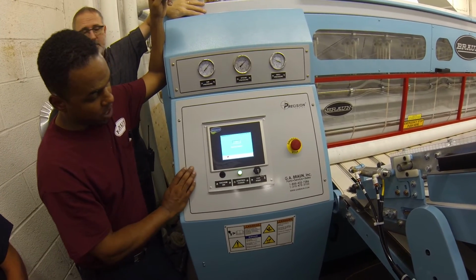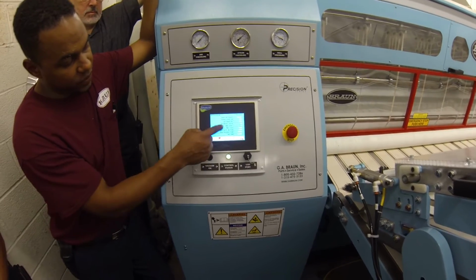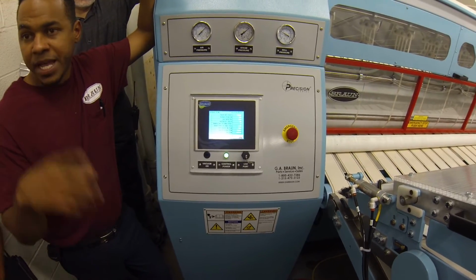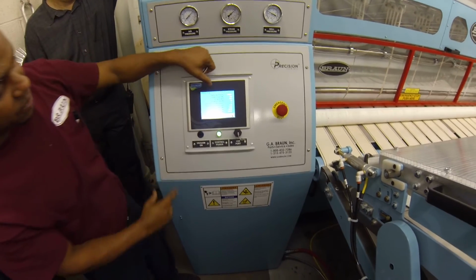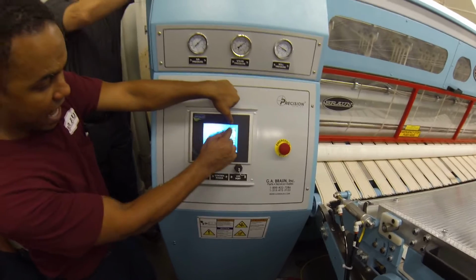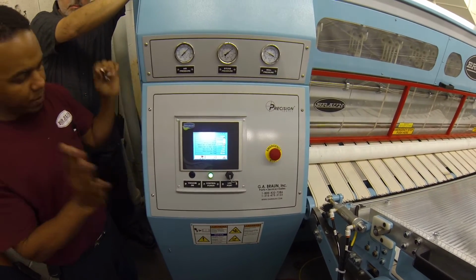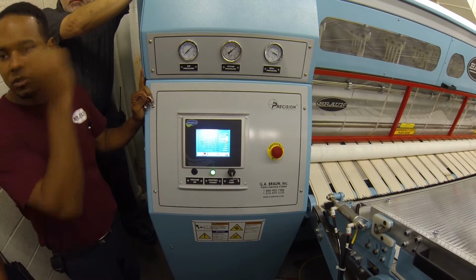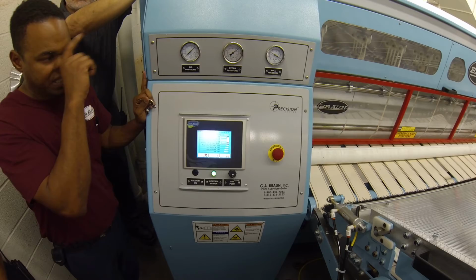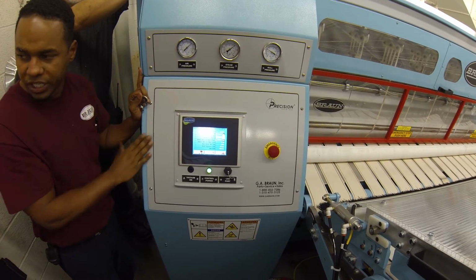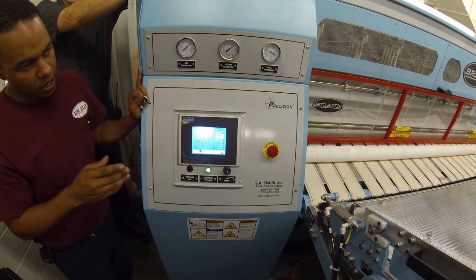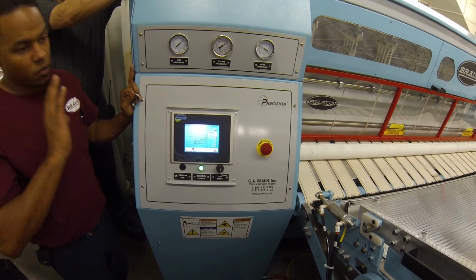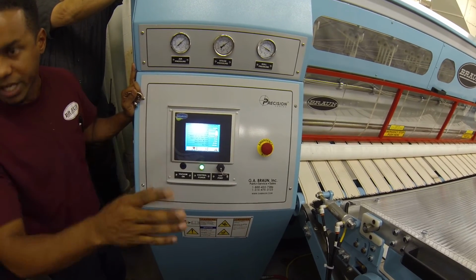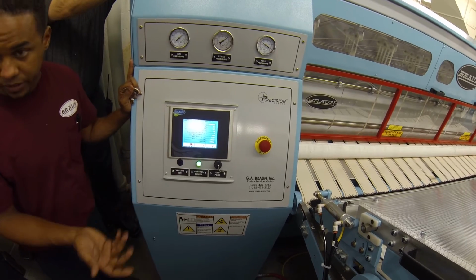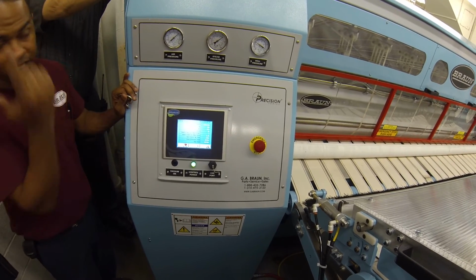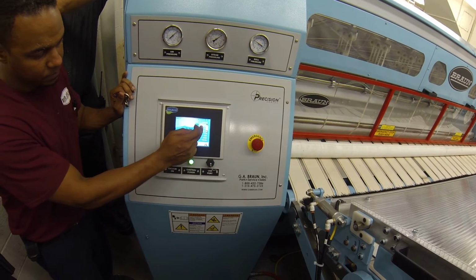On set 1, it will give you the screen where you can change the setting I was telling you about earlier - that right now we are depending on this one here. If you see a speed reference source, it says feeder. You can have 2 ways: if you do internal, it will depend on itself; if you do folder, it will depend on the one in the back. So the speed running from there, we send a signal out and output to this one to run. So basically, right now, let's say for some reason you're doing maintenance and you want to run - you come here and put it on either internal, if you want to manage the speed on this one, or to manage the speed on the back, or back to the form, or back to the feeder.